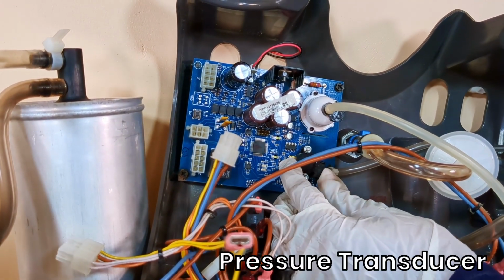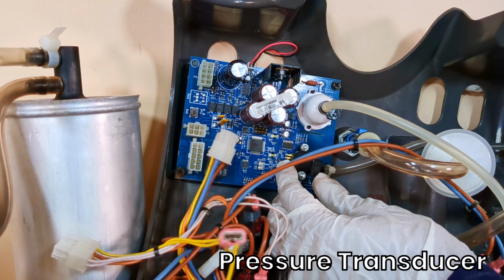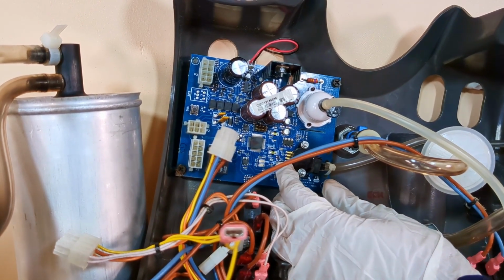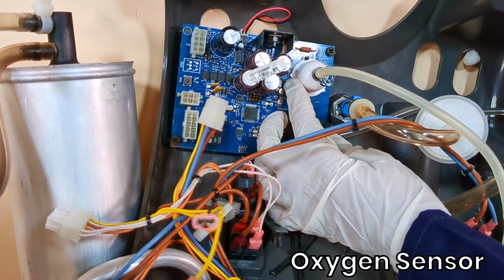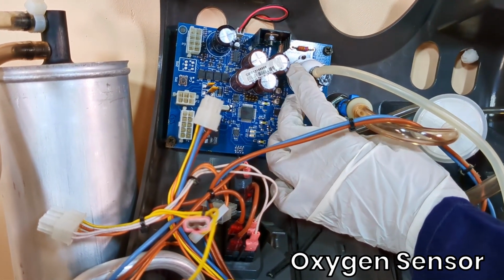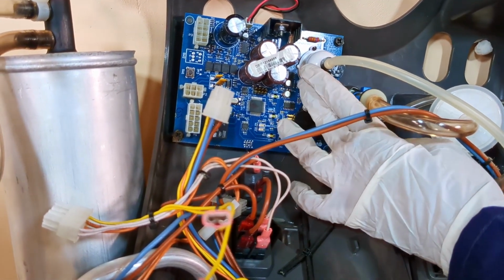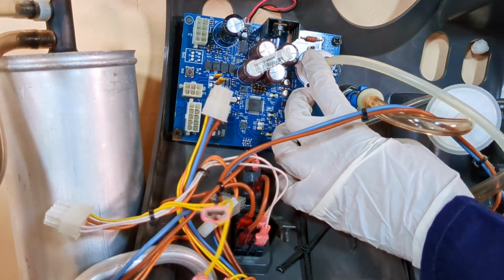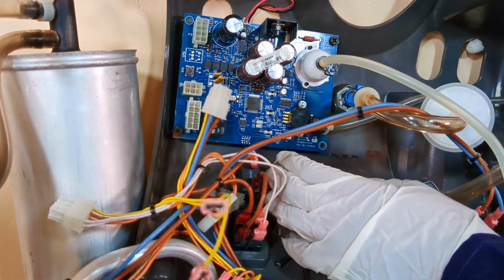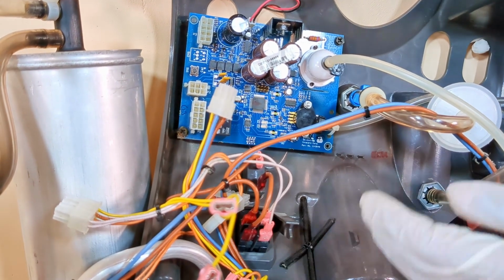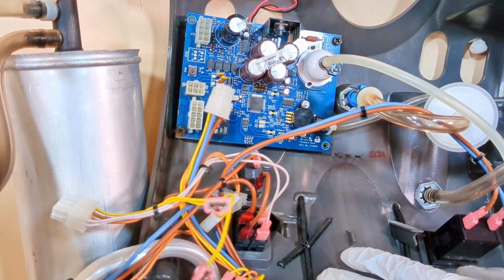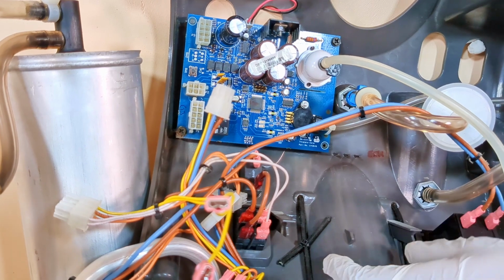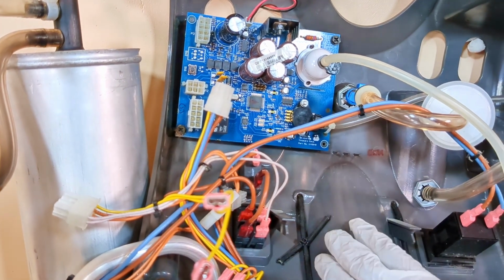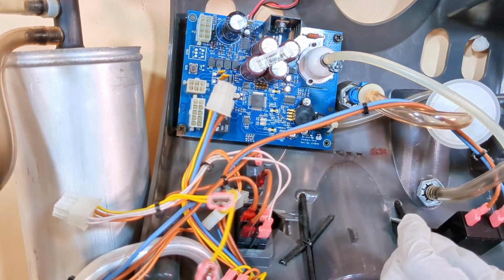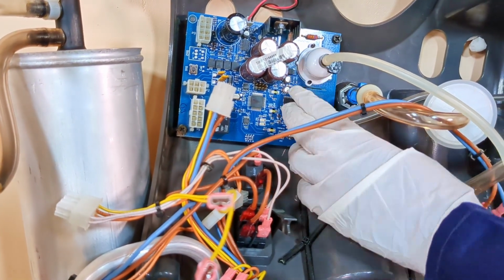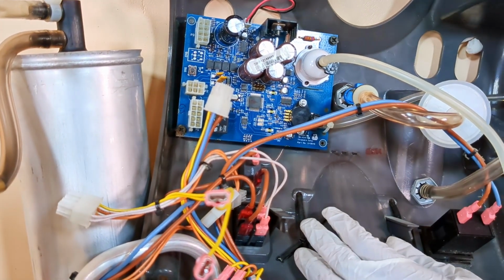This is the pressure transducer, and it is used to monitor the pressure conditions in the product tank. This is the oxygen sensor. It is a ceramic zirconia sensor, and it monitors the oxygen levels that are produced by the concentrator. The oxygen produced by the concentrator flows out of the product tank and into the flow meter, but a small flow of this oxygen is sent through a precision orifice to the oxygen sensor. Please find the technical overview of this sensor in the description below.